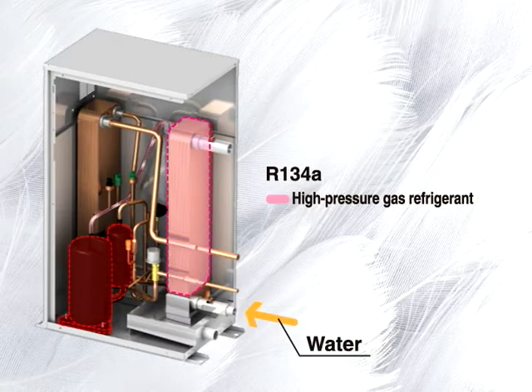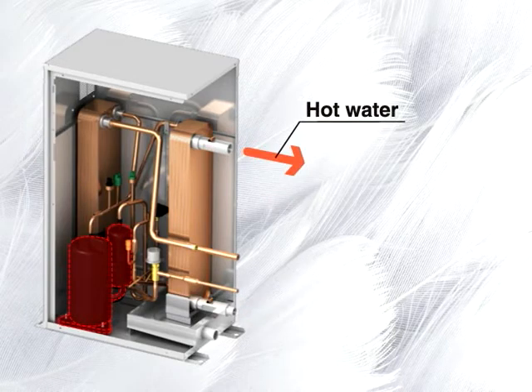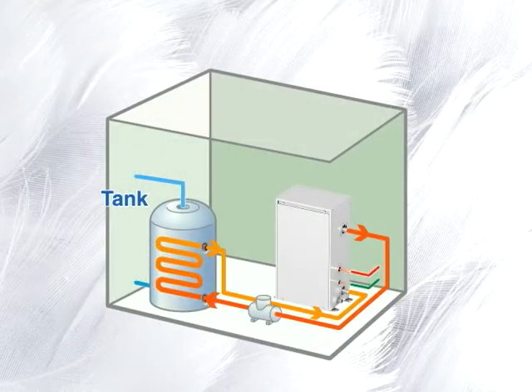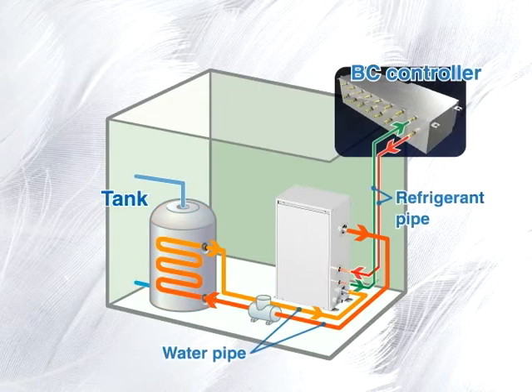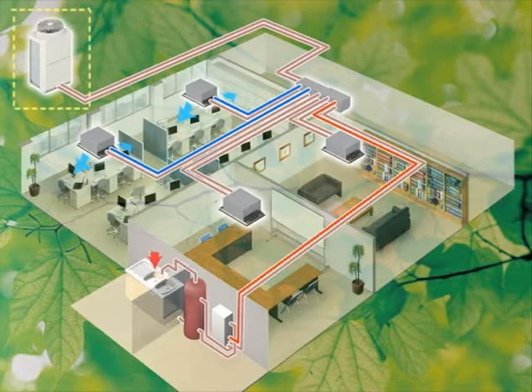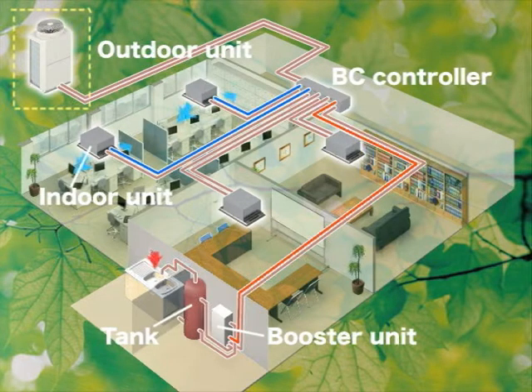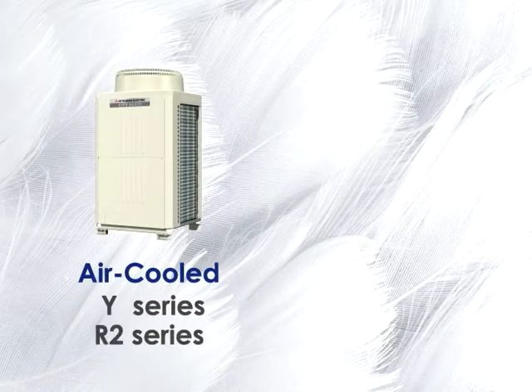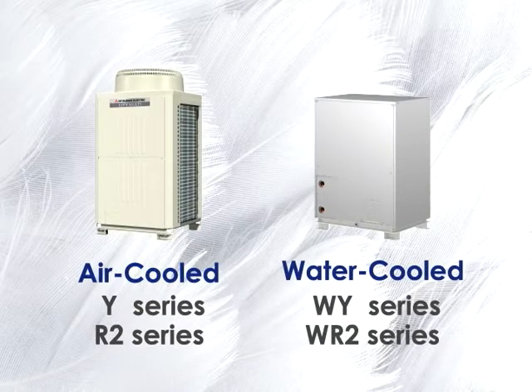To supply hot water, high-pressure R134A gas refrigerant exchanges its heat with the water entering the booster unit. The hot water circulates to heat the water inside the tank, which will be used for showers, floor heating, or panel heaters. In the full system, the booster unit is connected to a BC controller with refrigerant pipes and to the water tank with water pipes. And to complete the system, it is also connected to outdoor and indoor units. The air-cooled and water-cooled series outdoor units are connectable depending on the system structure.